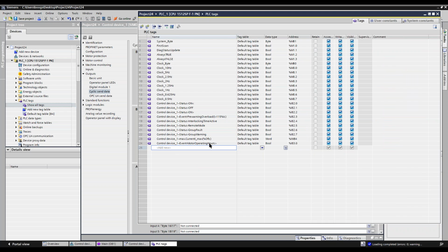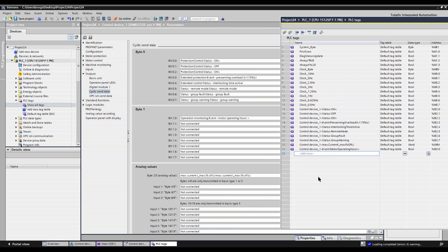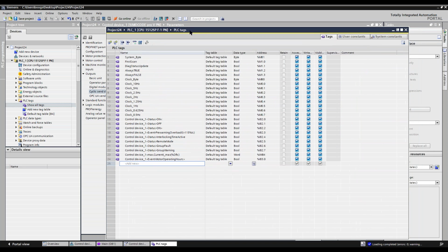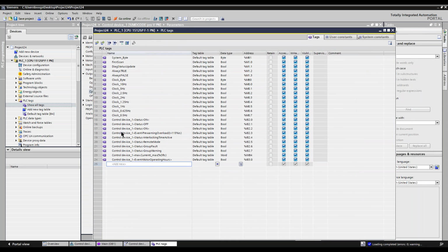There it is, event motor operating hours, and it's input 83.0. That tag gets automatically put in. Pretty slick. I think that is a huge time savings, the ability to get your program up and running quicker and reduce engineering time. Now there's a little bit more power to this, I'll show in just a few minutes, but this is a huge time saver for automatic tag generation. Now just a little step away from SIMOCODE, our soft starters do the same exact thing, just FYI.